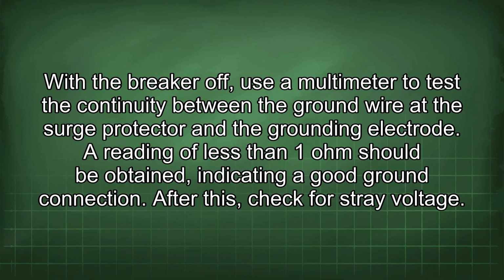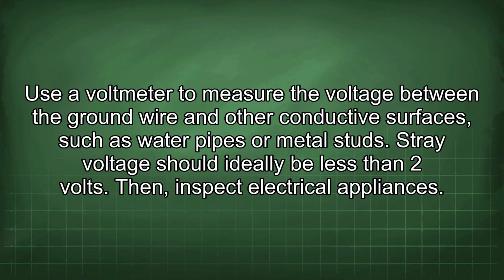After this, check for stray voltage. Use a voltmeter to measure the voltage between the ground wire and other conductive surfaces such as water pipes or metal studs. Stray voltage should ideally be less than 2 volts.